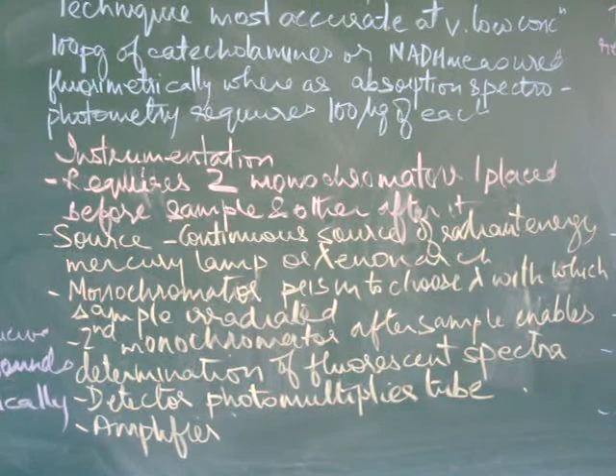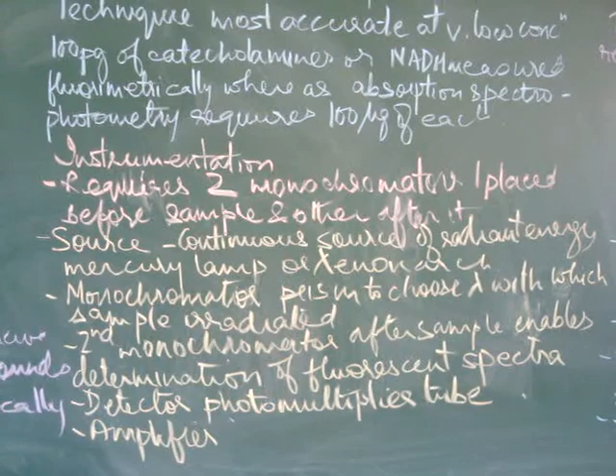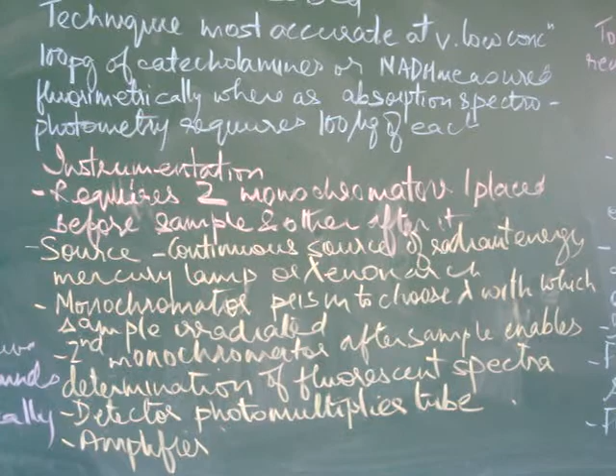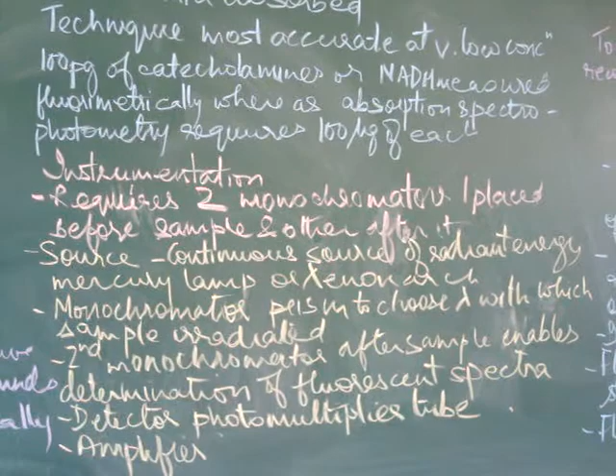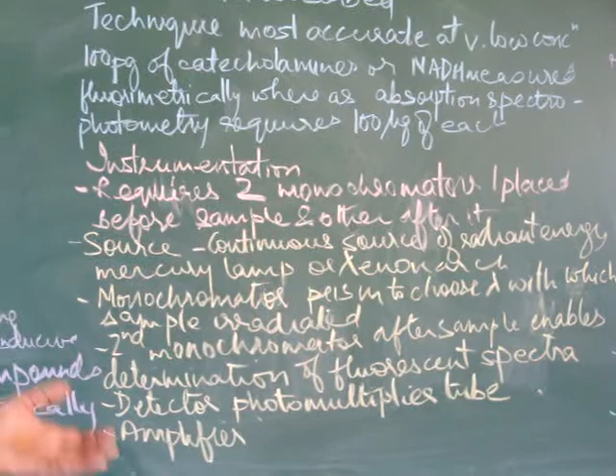The first monochromator chooses the wavelength with which the molecule has to be excited, and the second monochromator after that chooses the wavelength which is measured for fluorescence. So the second monochromator after the sample enables determination of fluorescence spectra. The detector is a photomultiplier tube, and then an amplifier to measure the amount of emitted radiation.